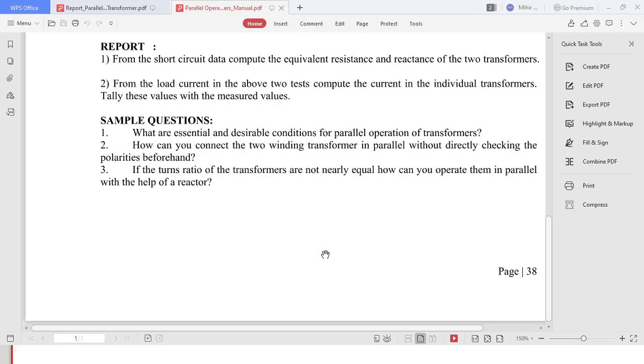How can you drop that voltage? You can drop this voltage by connecting an air core reactor in the primary side, right? Why air core reactor? This is a reactive device. Otherwise, you can do this by connecting resistance also. In this case, your power loss will be there. So it is better to connect an air core reactor. Now, if you make a drop of 10 volt, then actually 100 volt will appear in the primary coil. That will convert it to 220 volt in the secondary side. This way you can do that. This is the last part of this experiment. Thank you all.